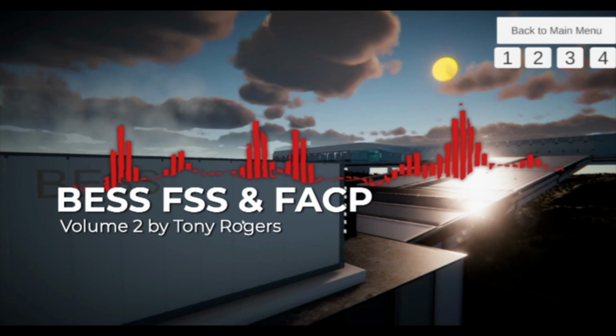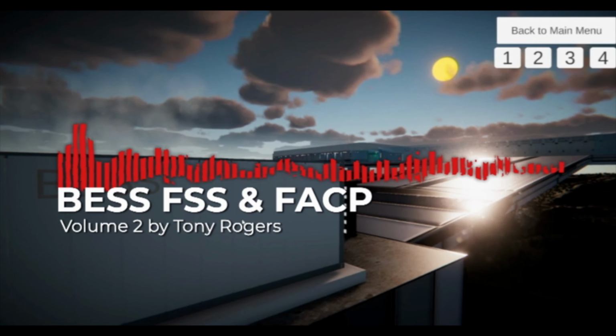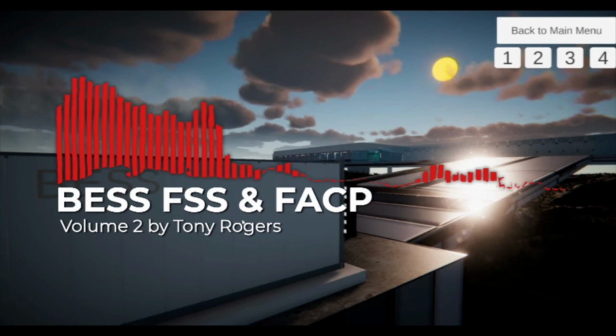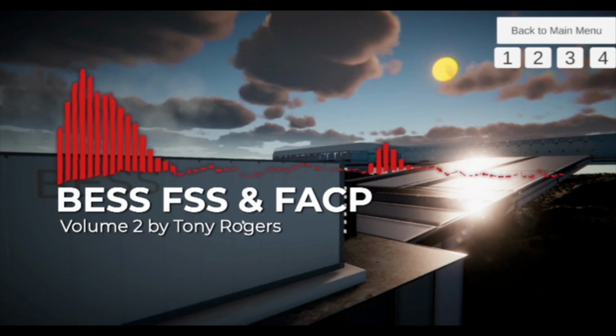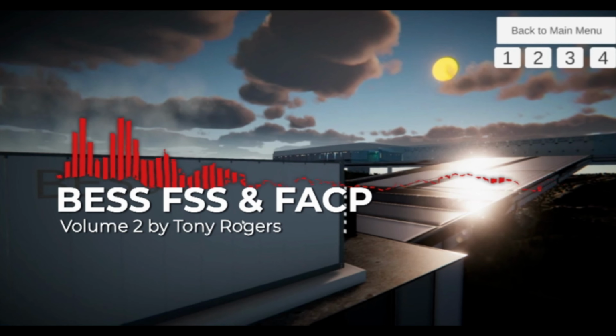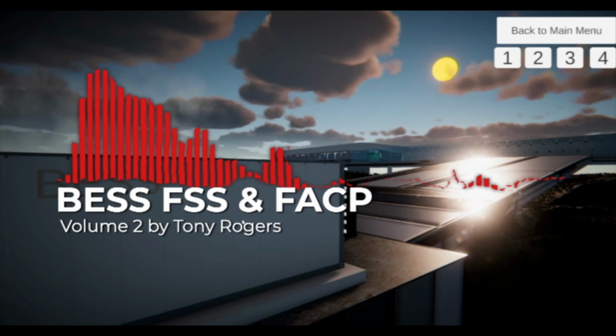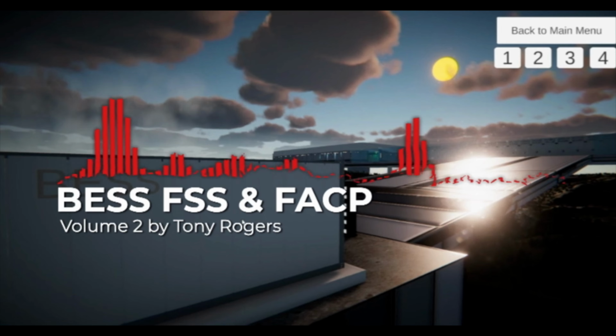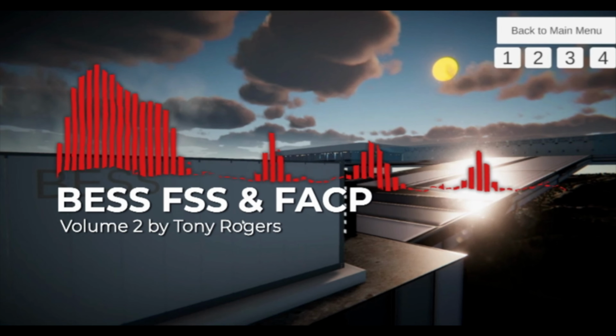The formula for CFM is CFM equals the area multiplied by the air changes per hour multiplied by the room height divided by 60. This formula takes into account the size of the protected area, desired air changes per hour, and the room's height.